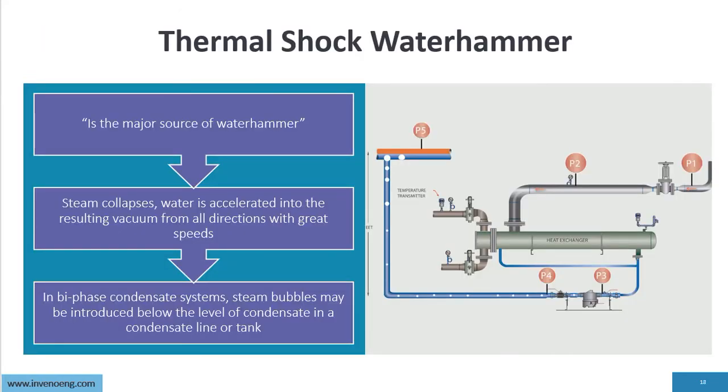Thermal shock is the major source of Waterhammer. The steam collapsing, water is accelerated into a resulting vacuum in all directions with great speed. In biphase condensate systems, steam bubbles may be introduced below the level of condensate in a condensate line or tank, resulting in Waterhammer. Now, a lot of times you hear ping, ping, ping, ping, ping, and that is that bubble collapsing.